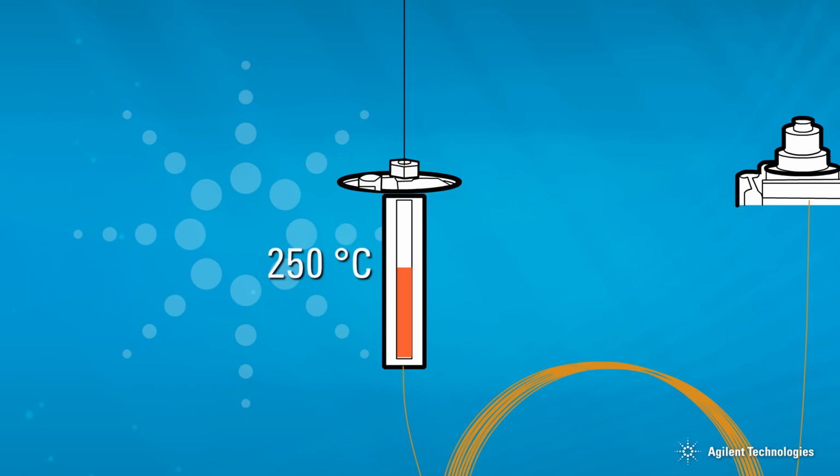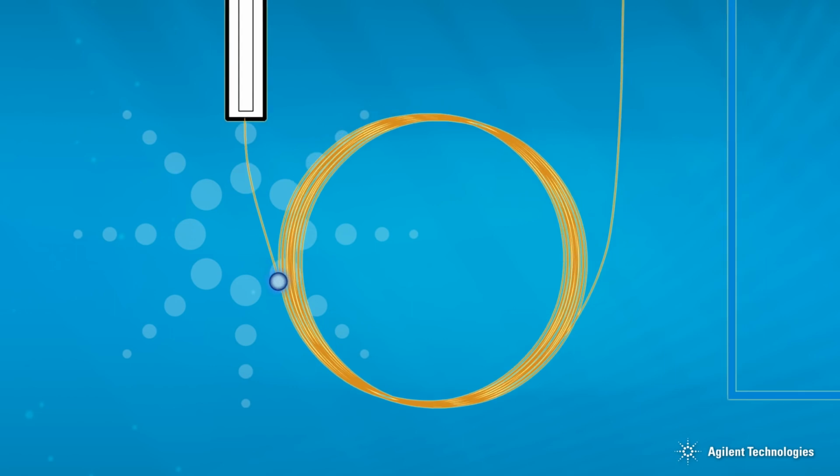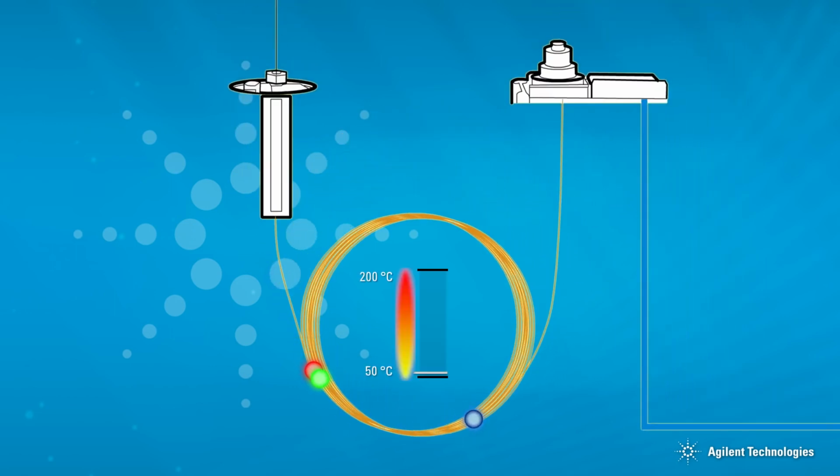When the sample goes into the heated inlet, it is very rapidly vaporized. This results in a momentary increase in the pressure inside the inlet. Once the sample is vaporized, it can then be swept into and through the column by the carrier gas. The sample moves in a tight band into the GC column, which is initially held at a low temperature.